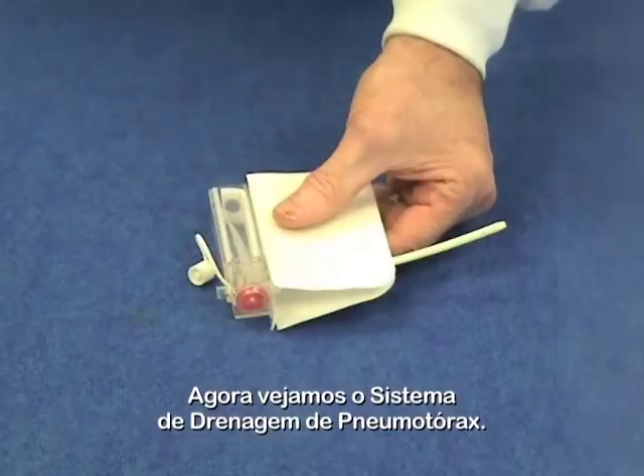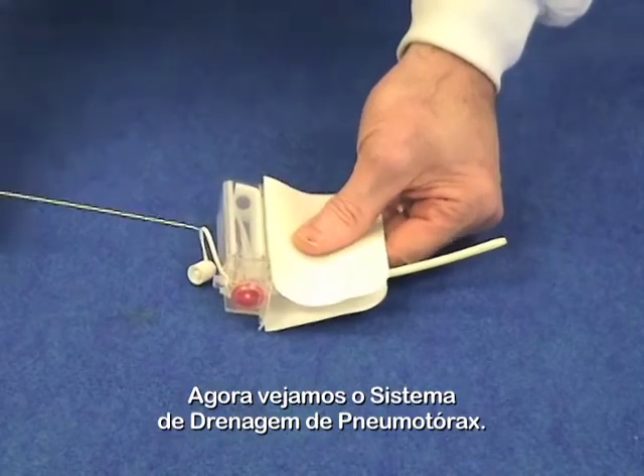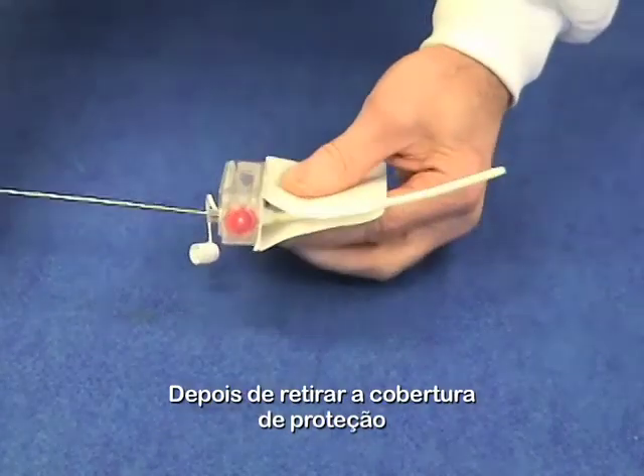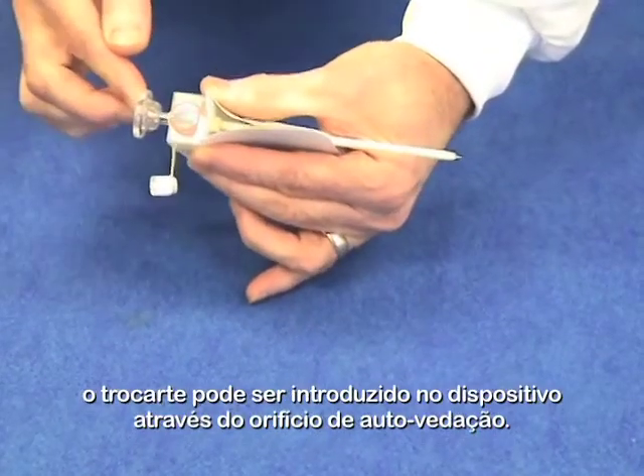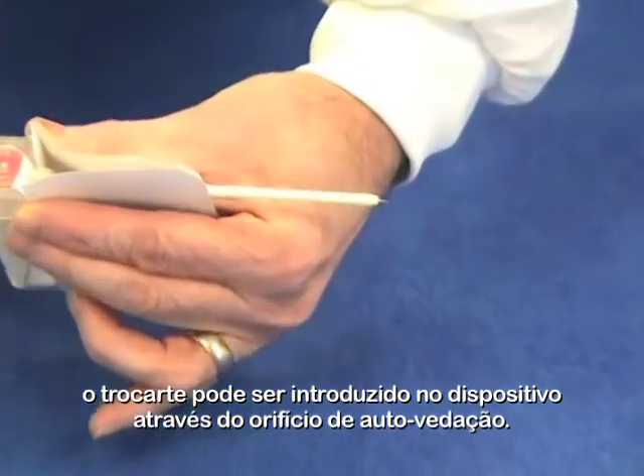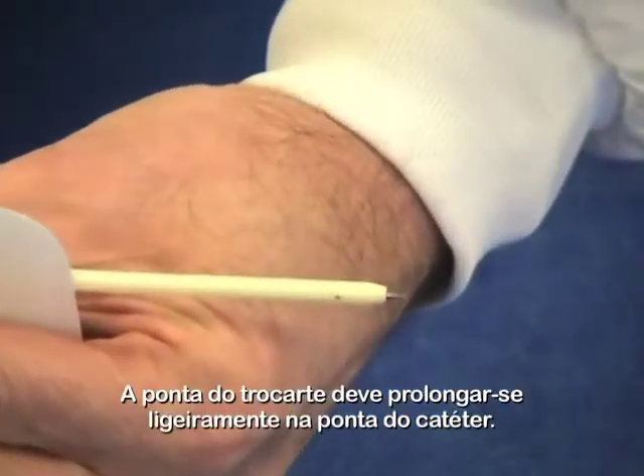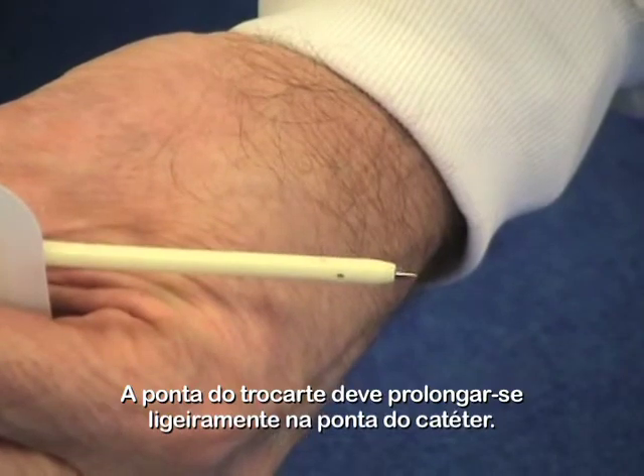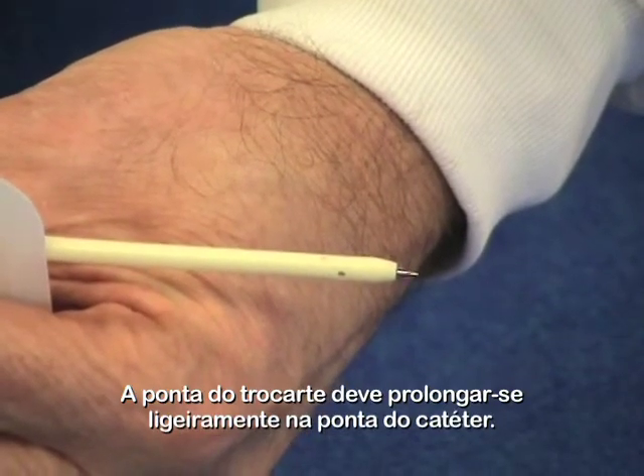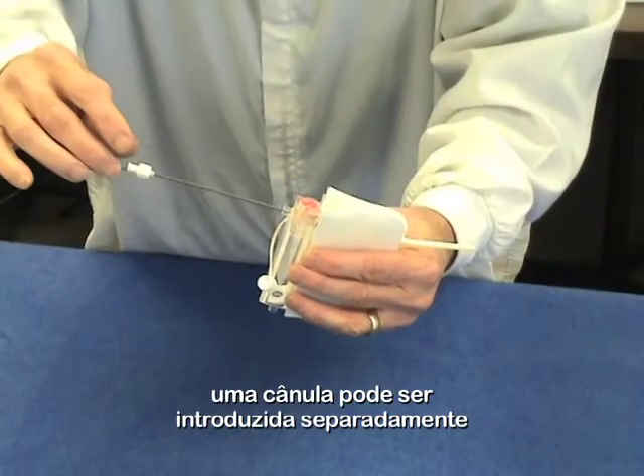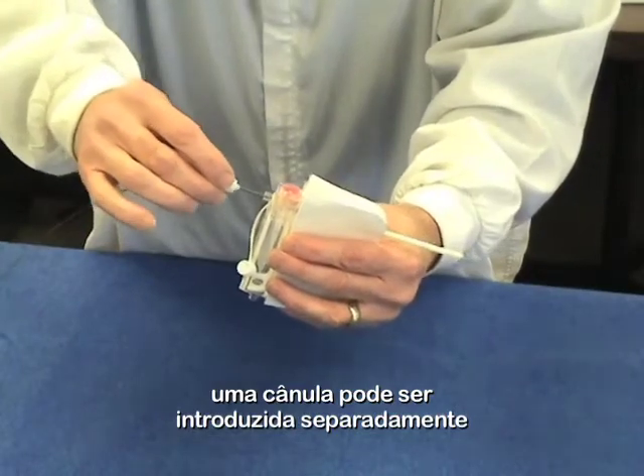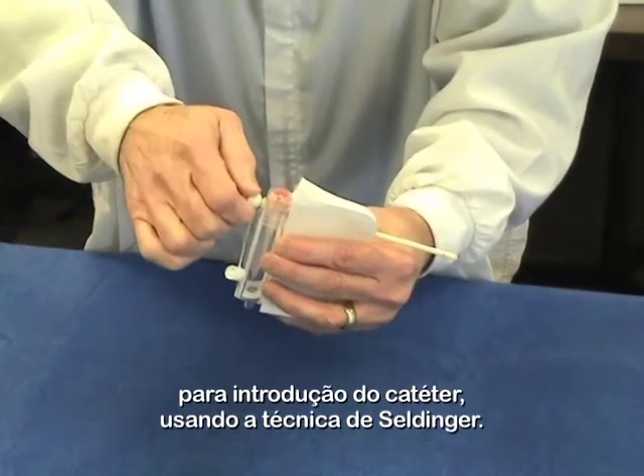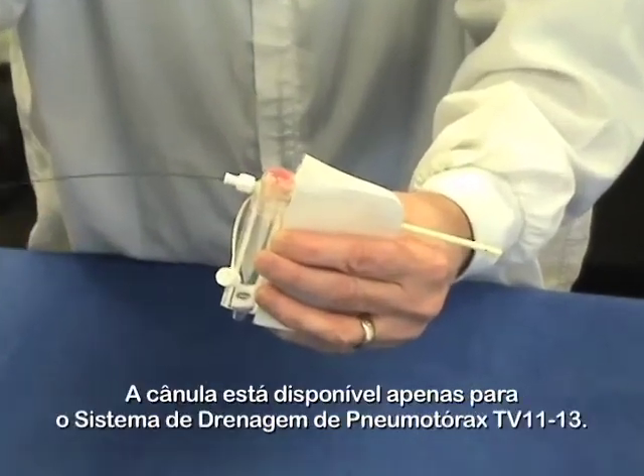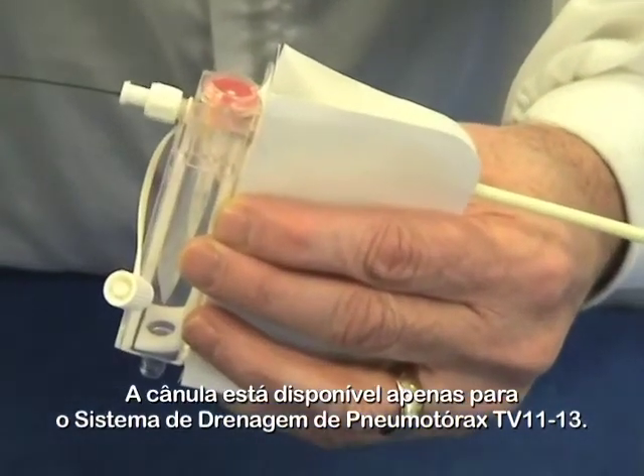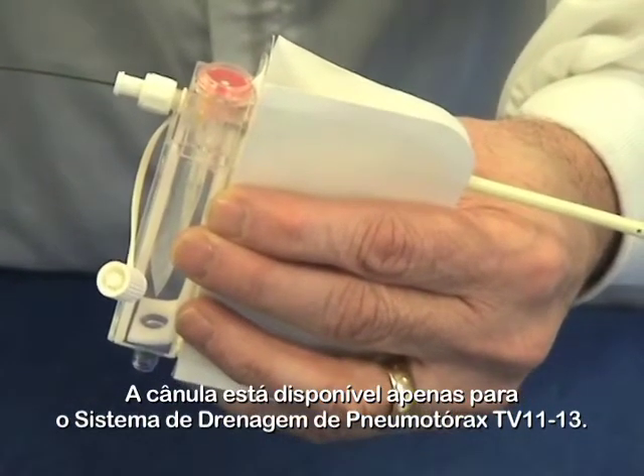Now let's take a closer look at the thoracic vent. After removing the protective cover, the trocar may be introduced into the device through the self-sealing port. The point of the trocar should extend slightly beyond the tip of the catheter. An over-the-wire cannula can be purchased separately for introduction of the catheter using the Seldinger technique. The cannula is only available for the TV11-13 thoracic vent.